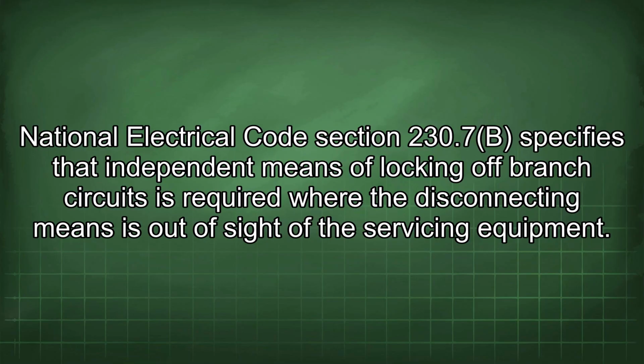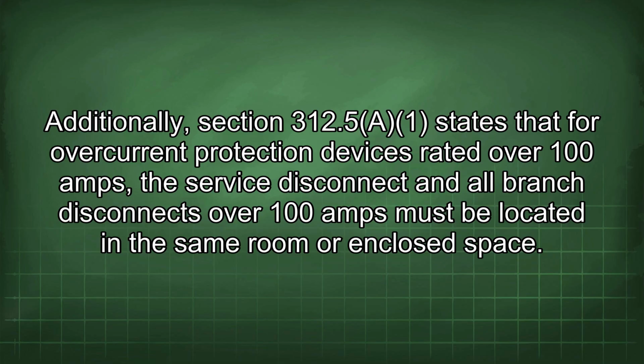National Electrical Code Section 230.7(B) specifies that an independent means of locking off branch circuits is required where the disconnecting means is out of sight of the servicing equipment. Additionally, Section 312.5(A) states that for overcurrent protection devices rated over 100 amps, the service disconnect and all branch disconnects over 100 amps must be located in the same room or enclosed space.